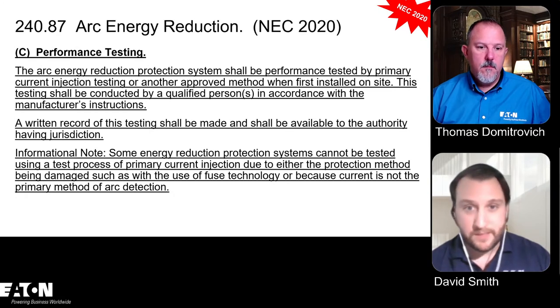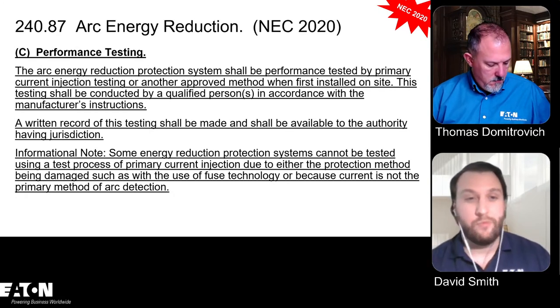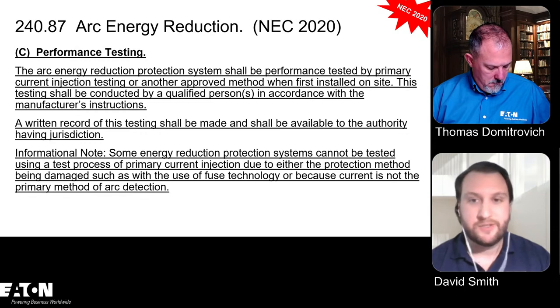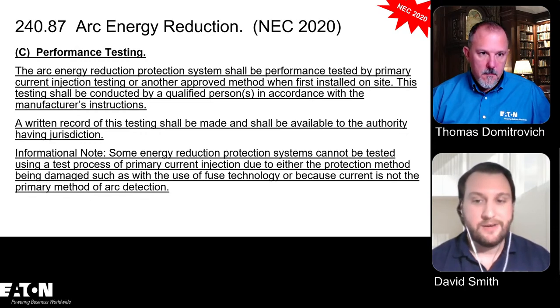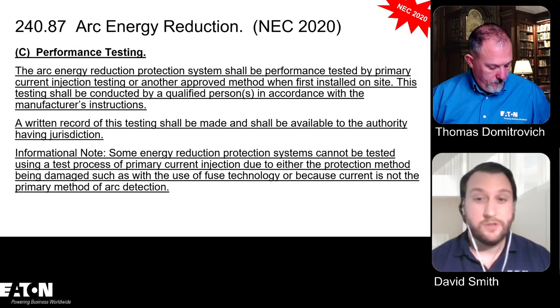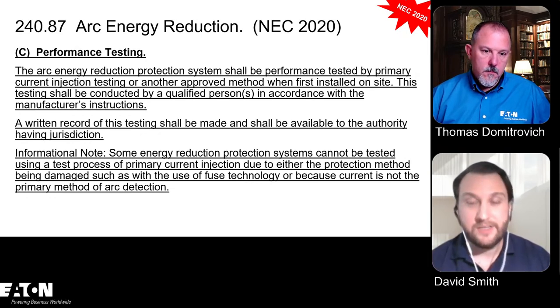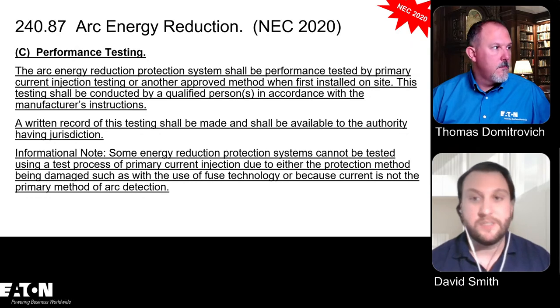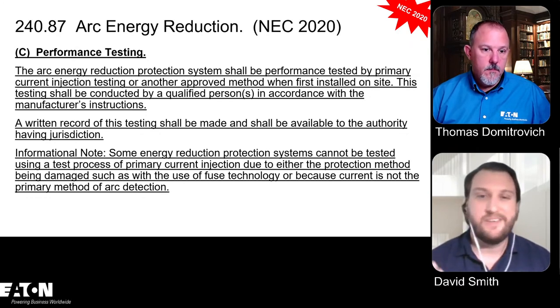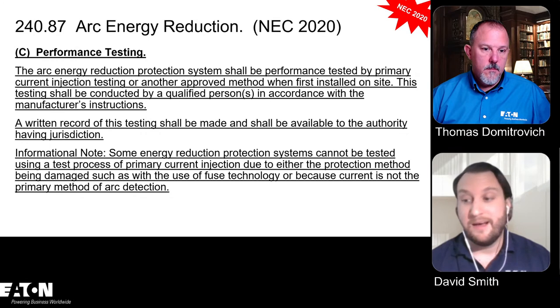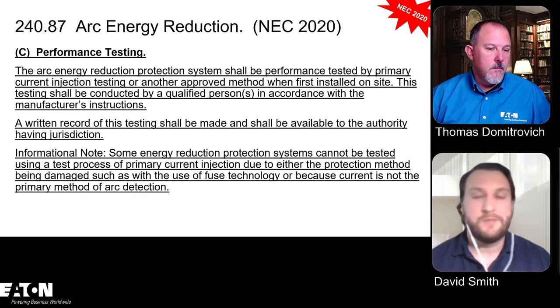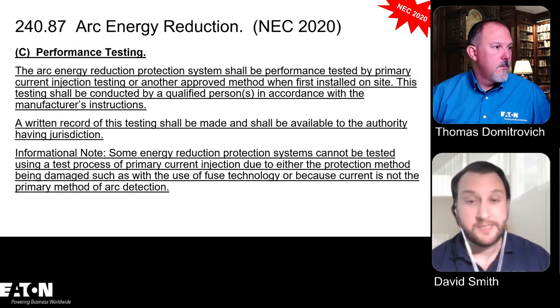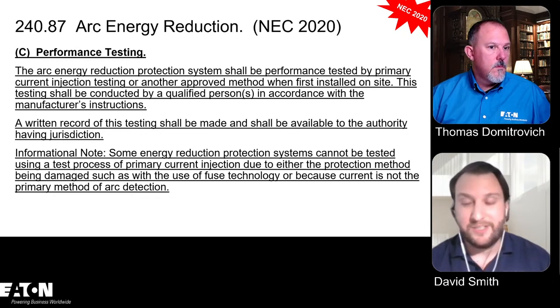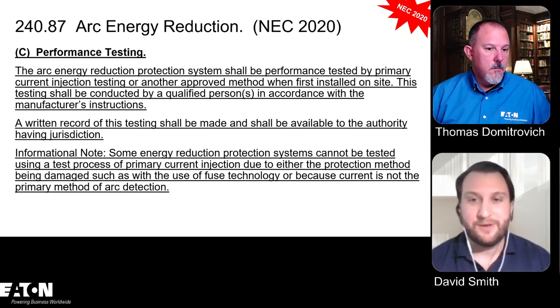then you can go ahead and do that. And so whenever it comes to Eaton's engineering services, we not only provide the primary current injection testing, but we also would say you can use secondary current injection testing for not only the circuit breakers, but the fuses as well. It's just different equipment, different obstacles you might have in the field. Because for primary current injection testing, I'm sure Tom is going to go through some of the equipment that you use for that kind of thing.